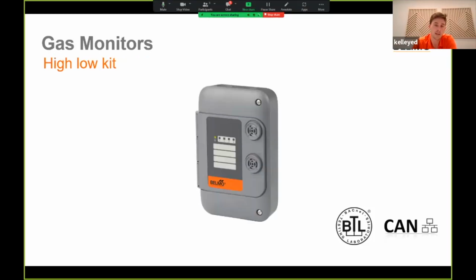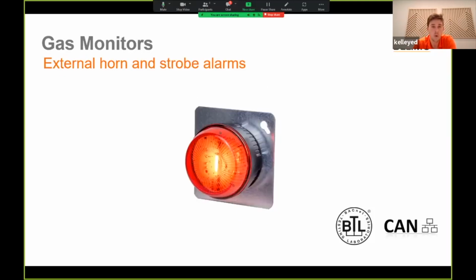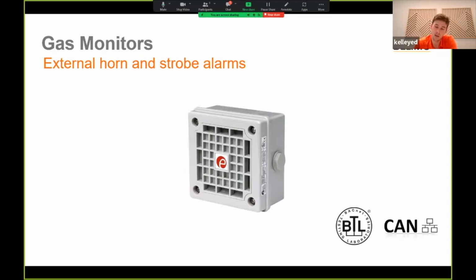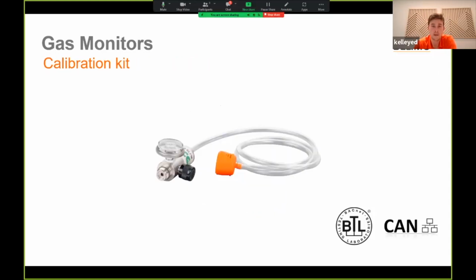We have a high-low kit. So this is essentially each gas monitor can monitor up to two different gases. If you're monitoring two gases with different densities, all this is an external shell that allows you to place one of the sensors in a remote location up to 7 feet away. We have external horn and strobe alarms that, in addition to the horn and strobe alarms on the gas monitors themselves, are louder and brighter if you need something like that.